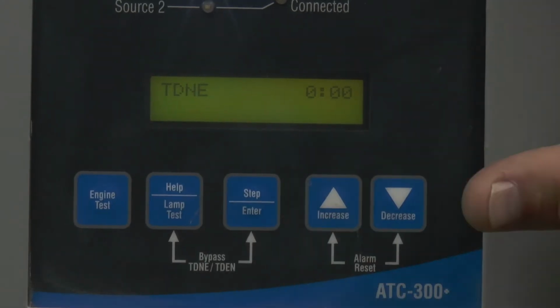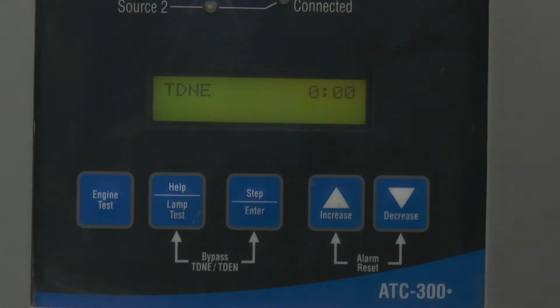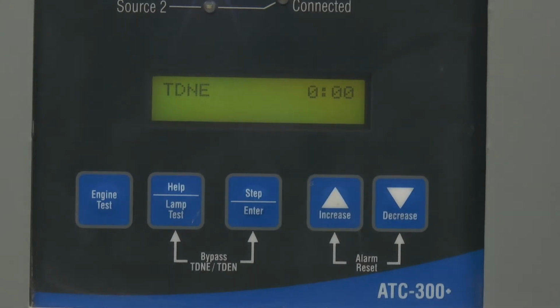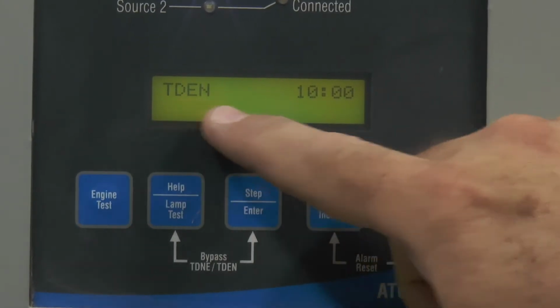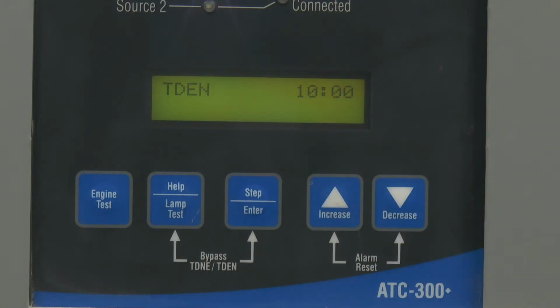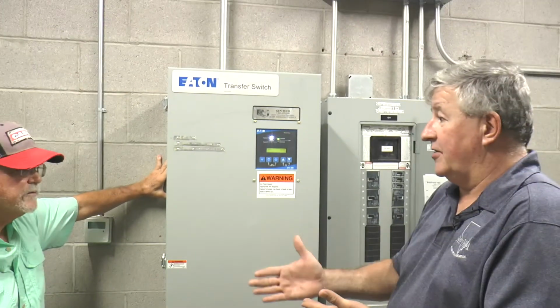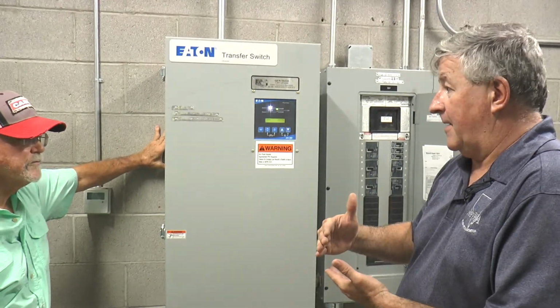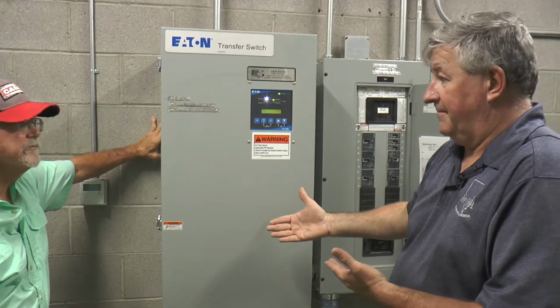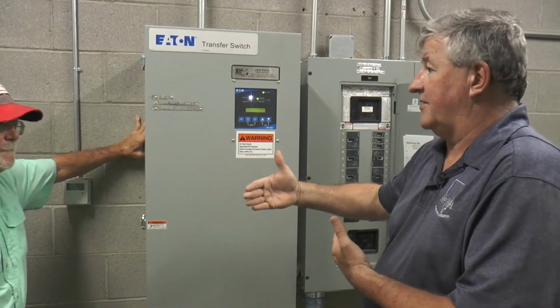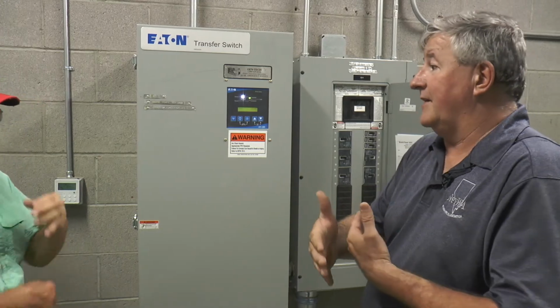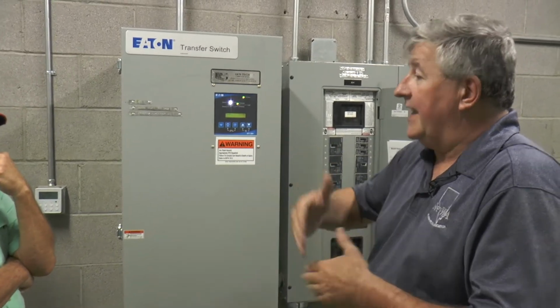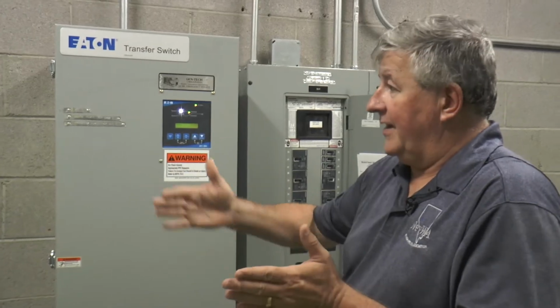Normal to emergency: once the generator comes to rated voltage and frequency, within 10% of it, the transfer switch will transfer over. Emergency back to normal: once utility power is restored, it will run for 10 minutes before the transfer switch will release the relay to tell it to go back. In that 10-minute period, at 9 minutes and 30 seconds, if there's another blip in the power, the timer will start all over again. It will not continue from that last 30 seconds. So you could be on the generator for 30 or 40 minutes if you have multiple outages during that retransfer period.